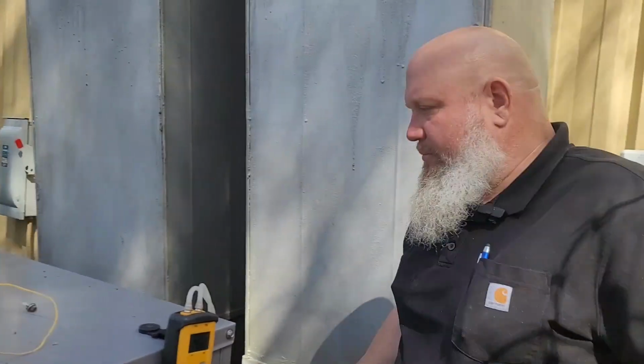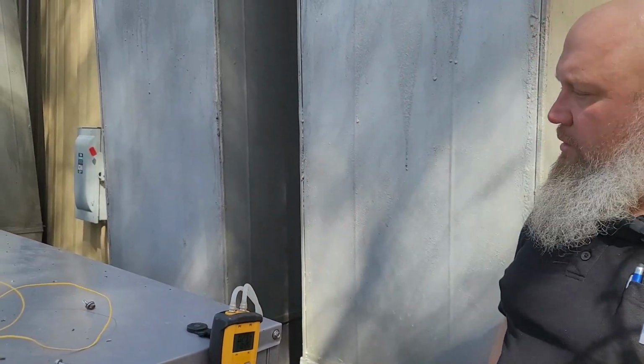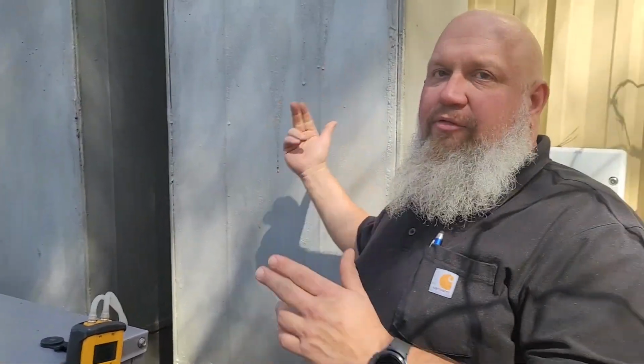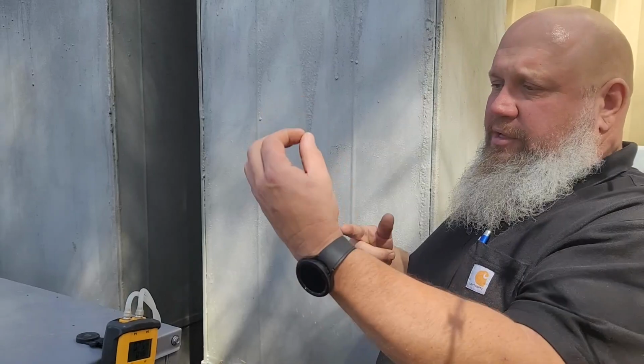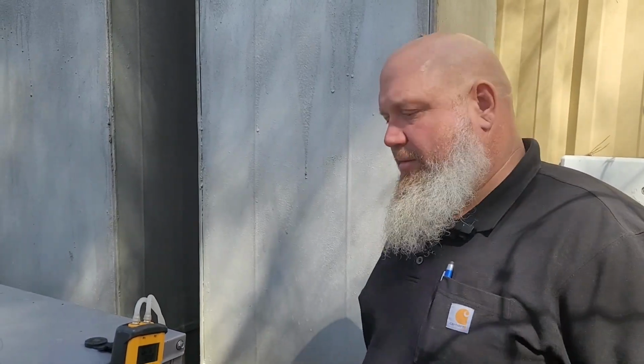Okay, and then that's the supply. Where does the arrow point with the return? Again, point toward the unit or toward the ductwork? Towards the ductwork, because the airflow is going towards the unit. Right. So you want that tip to be in the airflow. So in other words, a lot of people think that the arrow is the direction of air, but the arrow is the opposite of the direction of air. It points against the direction the air is flowing. Okay, into the air. Great.